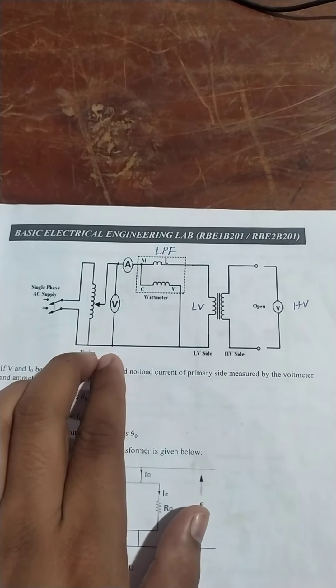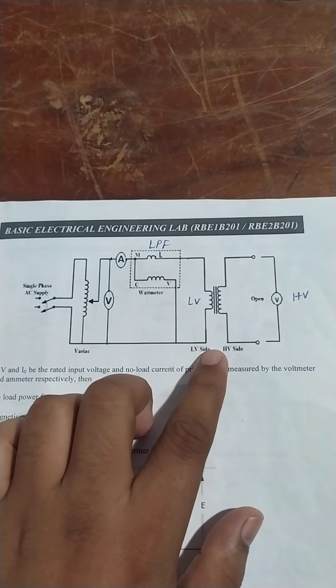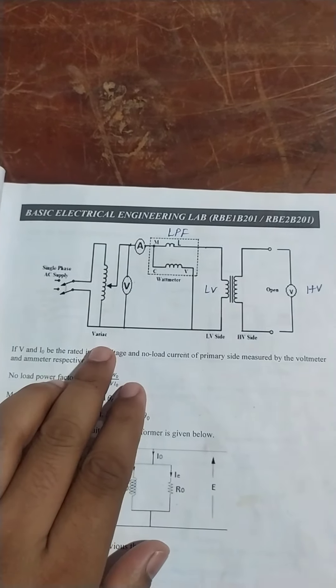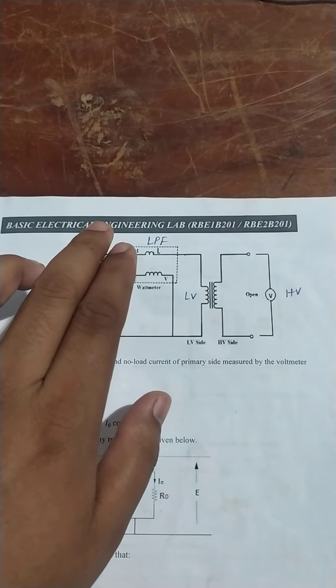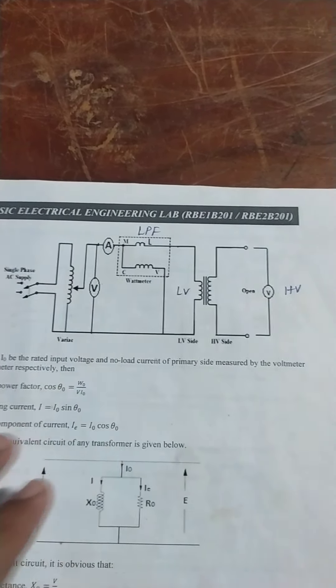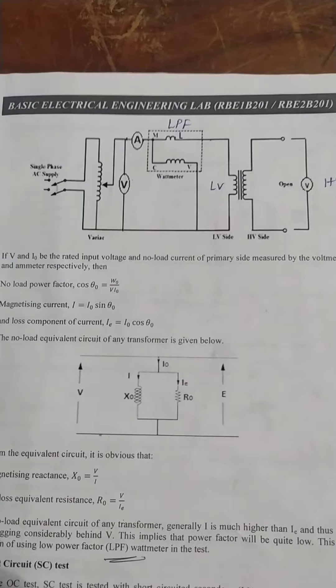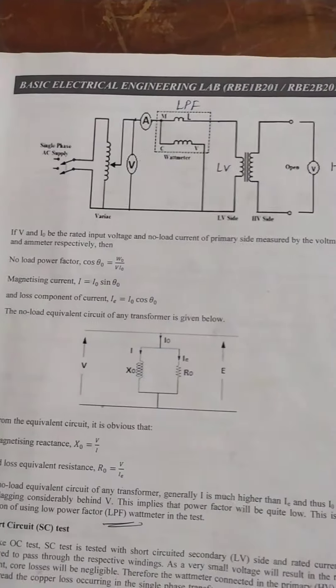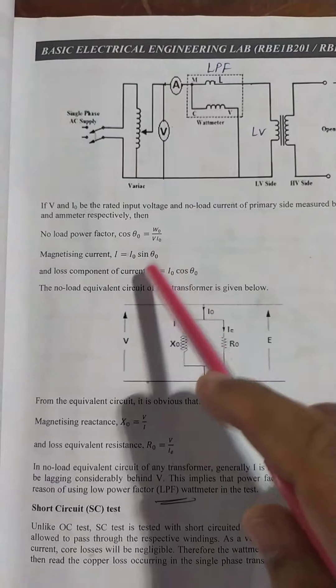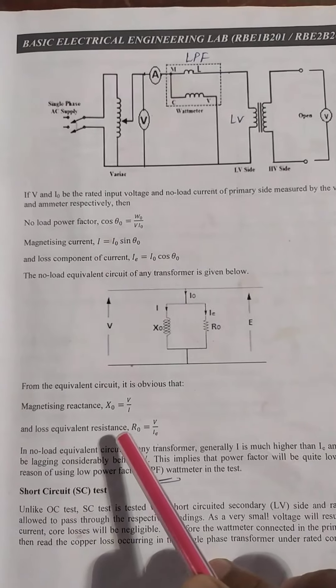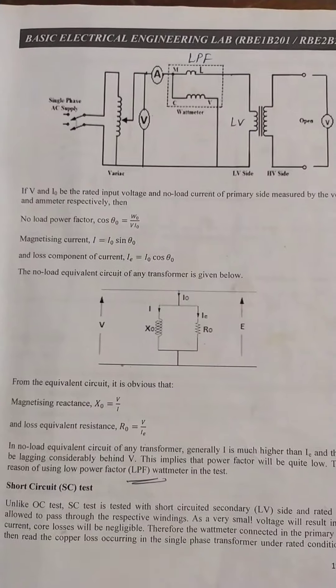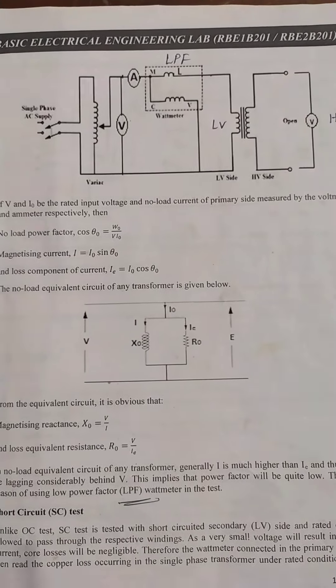We will be applying the rated voltage on the low voltage side, which is 115 volts for this transformer. We will be using an LPF wattmeter because in this condition the power factor will be quite low. By performing this test we can find out the no-load power factor, magnetizing current, and loss component of current, from which we can find the magnetizing reactance and loss equivalent resistance — essentially the core parameters and core loss occurring in the system.